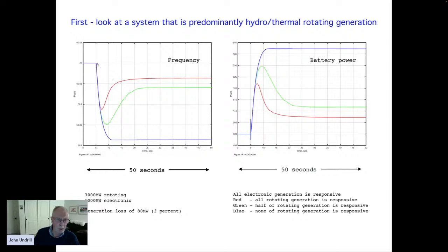So this is 2%, which is two large nuclear units disappearing in a 100,000 megawatt system. Frequency goes down. This is mislabeled. This is frequency. Starts at 60 hertz.